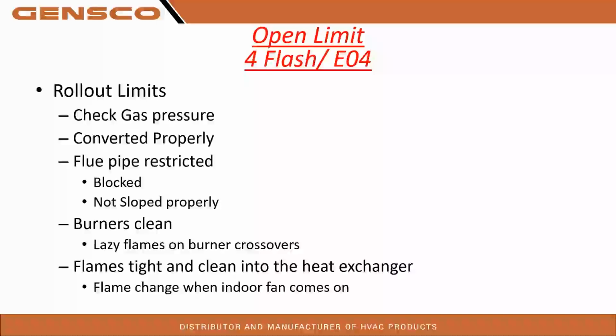out, right? So burners clean, lazy flames, or burner crossovers are dirty. Burners clean is a big one. Seen it before where we get a little bit of rust or something like that, and that flame isn't being pulled as good as it should, or it's kind of lazy, if you will, and the flame will stand up off the transfer a little bit and create some heat on that rollout limit.